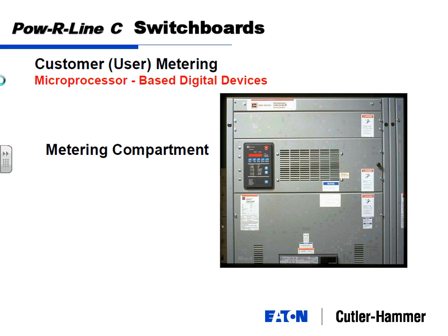the utility's giving you power, and they're billing you. And unless you've got a meter on, you're sitting back and trusting that the utility must know what they're doing because they're billing me every month. I'm paying it and everybody's happy. Well, sometimes utilities make mistakes. And if you can catch them by putting in a $3,000 meter, and find out they made a $50,000 error on the power factor penalty they were billing you on, well, you could pay for that and the company Christmas party.